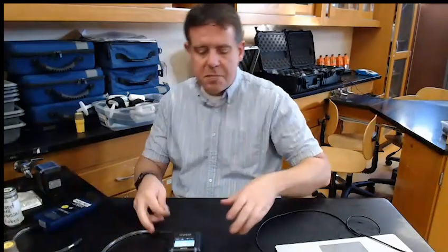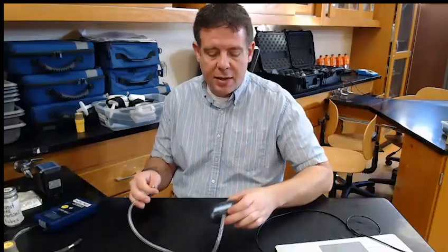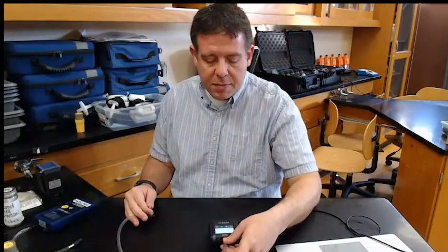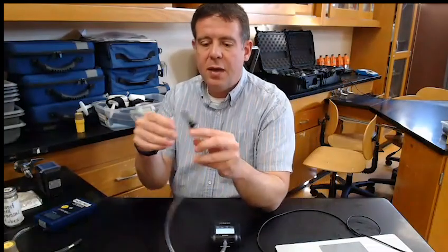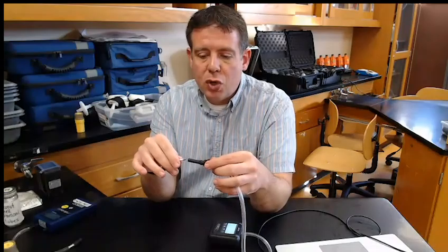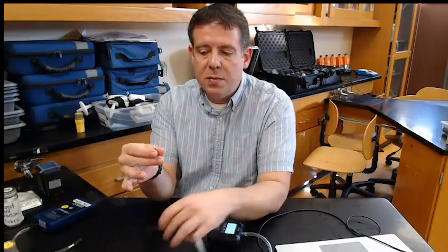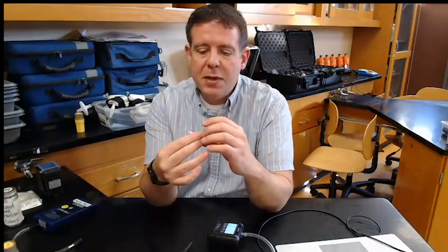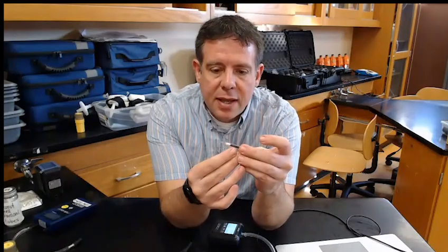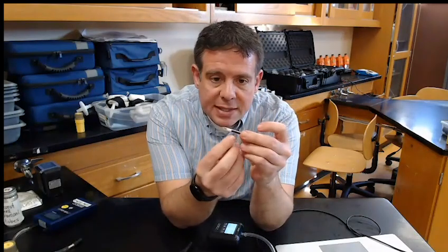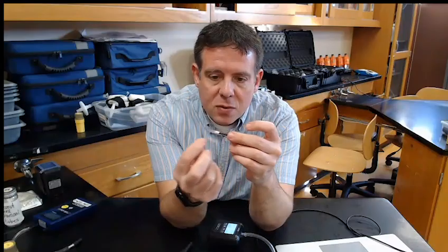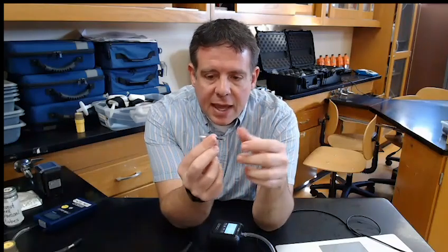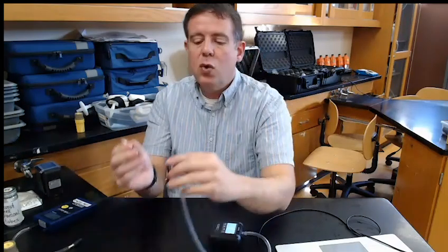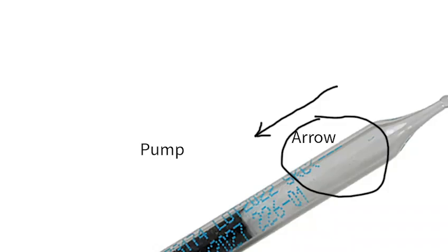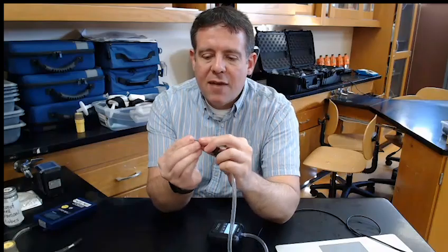When you're hooking up the sampling train, from the pump we have these little adapters to hook to the tubes. On these absorbent tubes there are arrows, and it's going to be pretty hard for you to see. But this arrow is going that direction towards my left hand. So you want that going towards the airflow, so to the pump. Remember that pump is sucking air. So we're going to have a good connection.